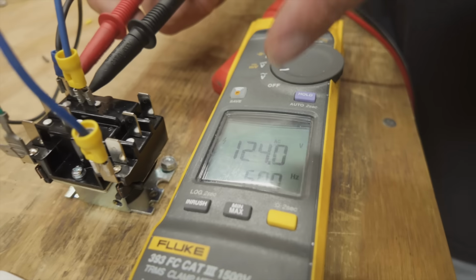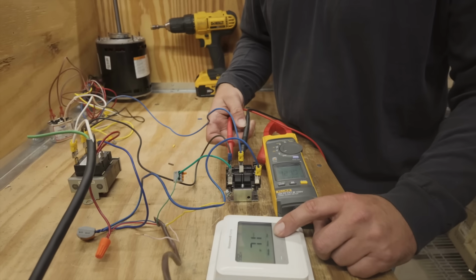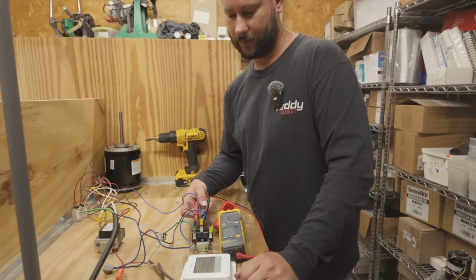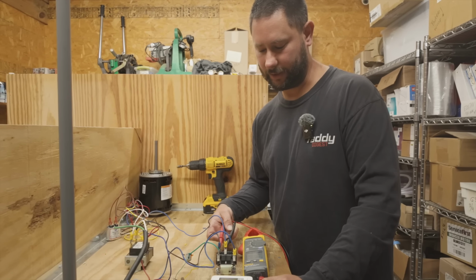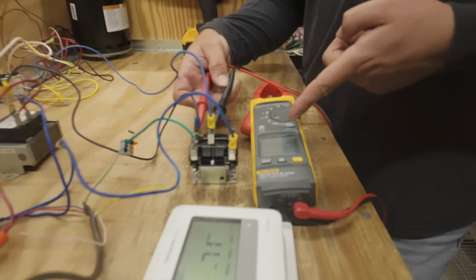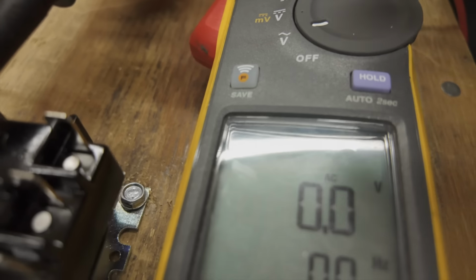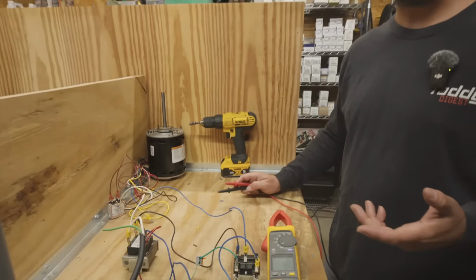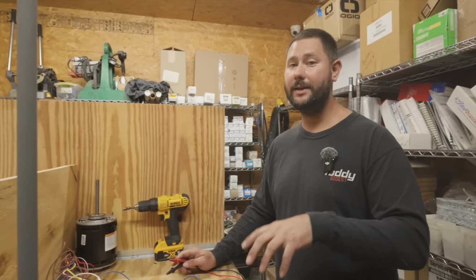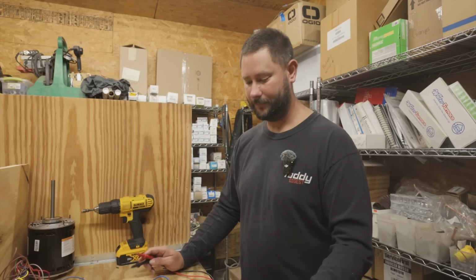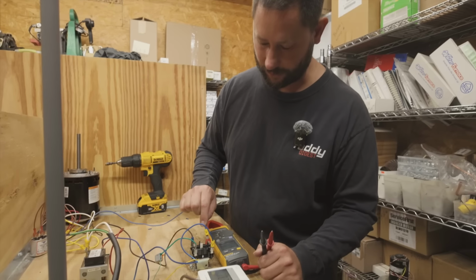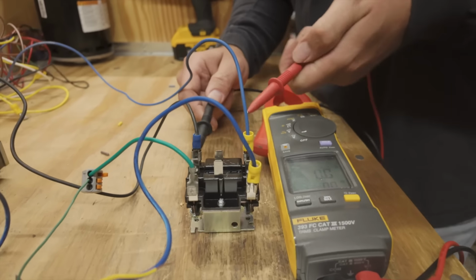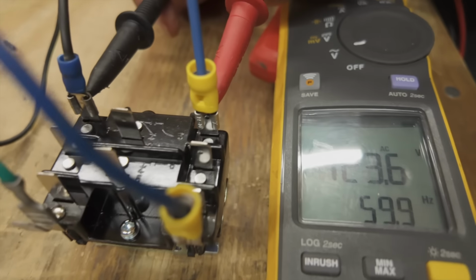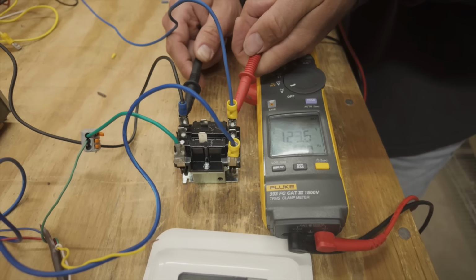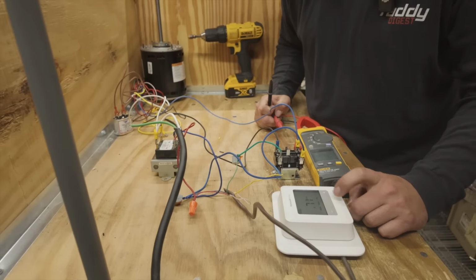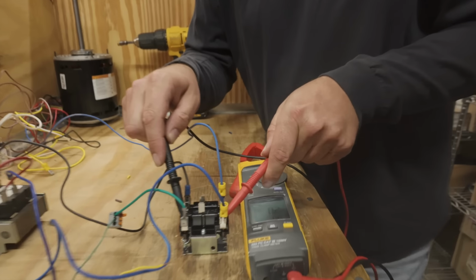And when it's open, you can see the voltage, right? 120. And that's another thing you need to know. If I take and I open that, I'm sorry, it's open now. Now I'm going to close it again. Look, 0. Knowing how to check the relay, there's several ways to check, right, using your meter. So knowing all those ways is going to help you in the field. So I want to show you that. Now, we're going to take this wire and put it on the normally open. When we put it on the normally open, we can read the voltage. All right? We can read the voltage. Now, we're going to turn fan on, send 24 volts to the coil again.